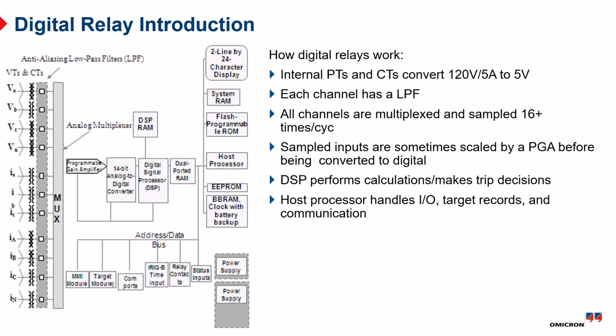Key thing here, though, is that in this particular device, you'll notice there are no parts in there for, say, the undervoltage pickup. We have signal acquisition parts, we collect the voltage, but that comparison to the setting is actually done here in the DSP. So we feed the voltages in, and the DSP, kind of like your pocket calculator, crunches the numbers and compares the numbers and generates an output: yes, I'm above the pickup, or no, I'm not above the pickup, and tells the host processor if the host processor needs to do anything.